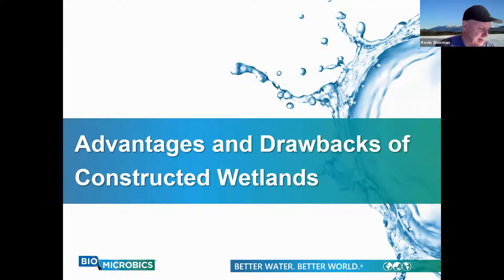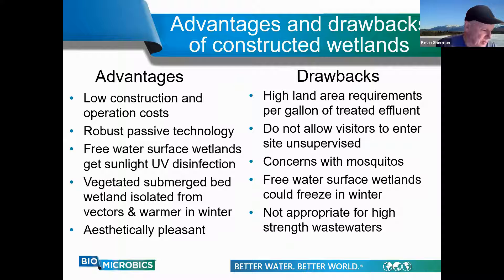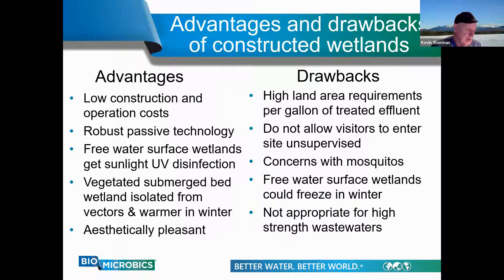There are advantages and drawbacks to the constructed wetland system. Advantages are in the left-hand column and disadvantages in the right. Freezing concerns, mosquitoes, keeping unsupervised visitors away, and UV disinfection by sunlight are all attributes of the free water surface wetland. Both constructed wetland types require lots of land, are aesthetically pleasing and robust, and are inexpensive to construct and operate by hard-working but less trained individuals. Neither type is a good fit for treating high-strength wastewaters or on very small lots.